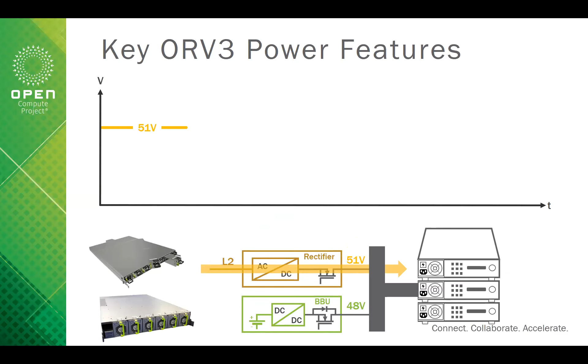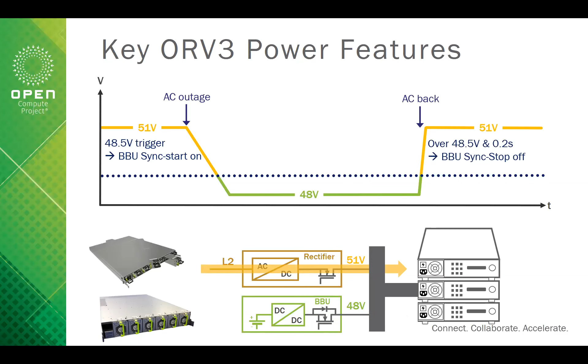So when AC is available, the PSU regulates the output from 51 to 50.5 volts. In this condition, the BBU is in standby mode and charges its output capacity close to the bus bar voltage. Once AC outages and the power supply output voltage drops by 3 volts, once output voltage is lower than 48.5 volts, it triggers the BBU to enable sync start, moving from standby mode to discharge mode. When AC recovers, the power supply will sync stop and increase output voltage to provide power to the IT load, and the BBU can go back to charge and standby mode.